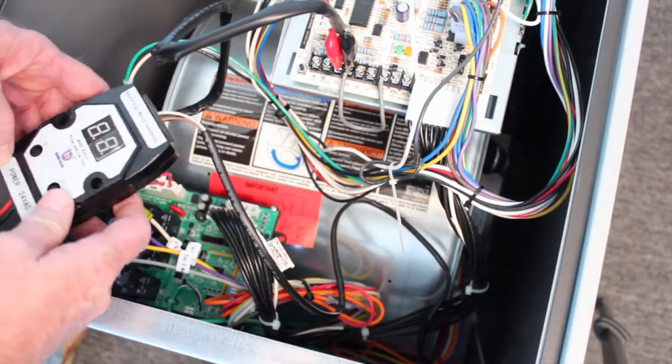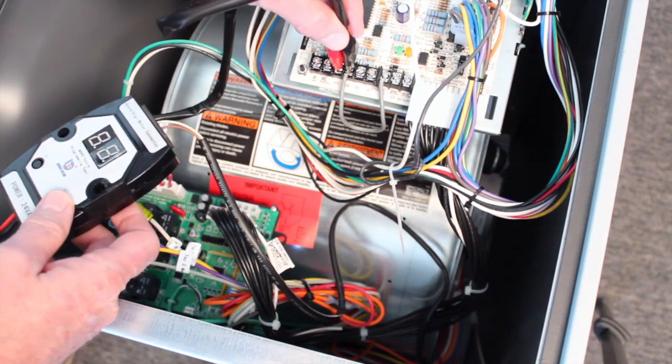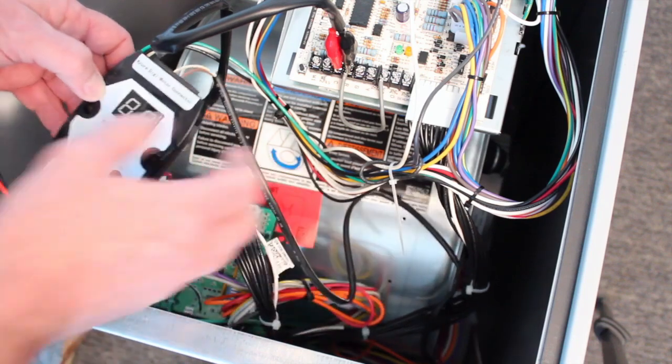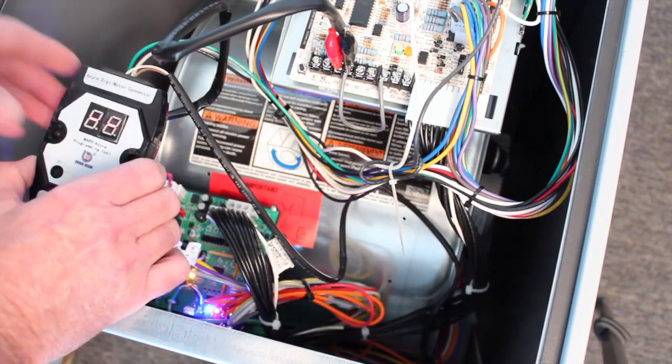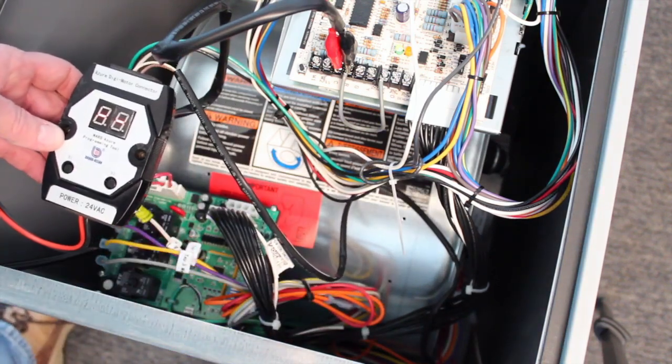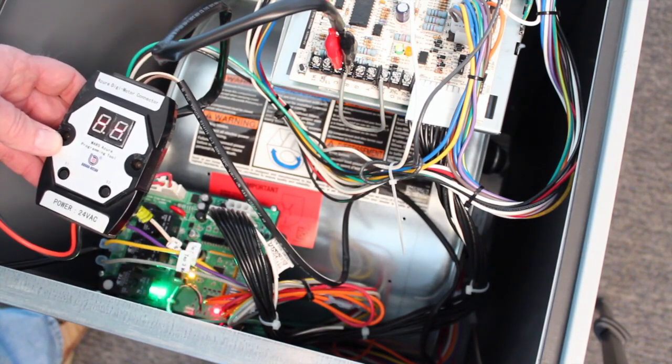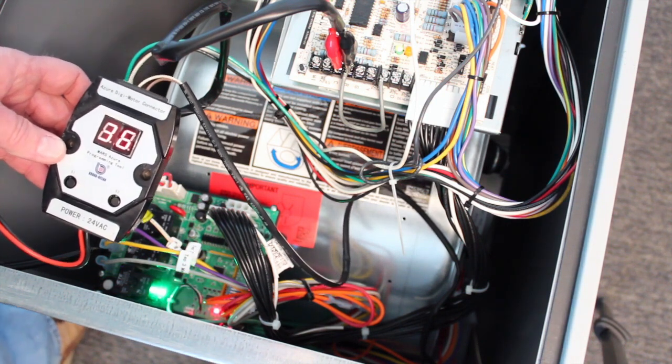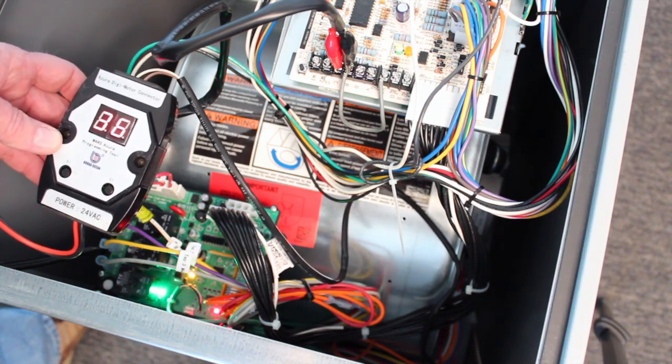With the power off, I've got the programmer attached to a 24 volt source and the other end is plugged in to the ECM motor. We'll flip the power on to the unit. The programmer is going to display the amount of torque that the motor is currently applying on this particular speed tap. So right now it's at 36% of its maximum torque.